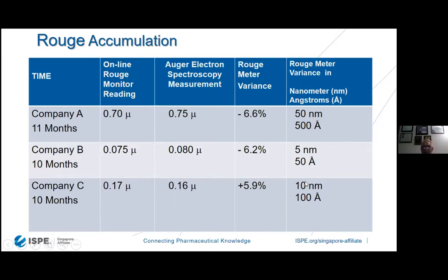And the point is that these different water systems rouge at different rates for different reasons. You can't blanketly say that I'm going to do a derouging passivation every year. As an example, what you need to do is to say, look, my nanometer level, as example on company B, is only 75 nanometers. I don't want to do a derouging passivation until I reach 300 nanometers or 400 nanometers or 1 micron or whatever is going to be discernible between you and QC, QA.